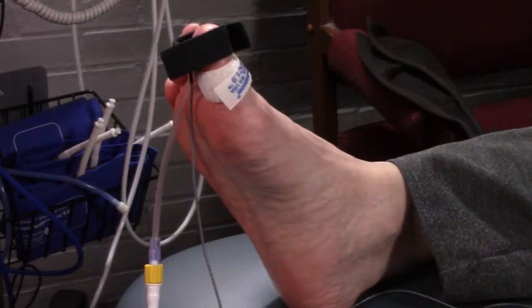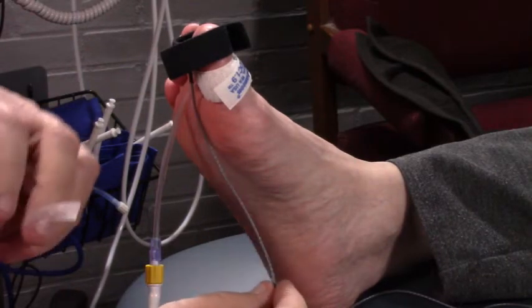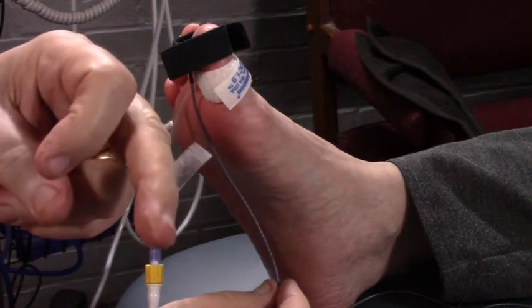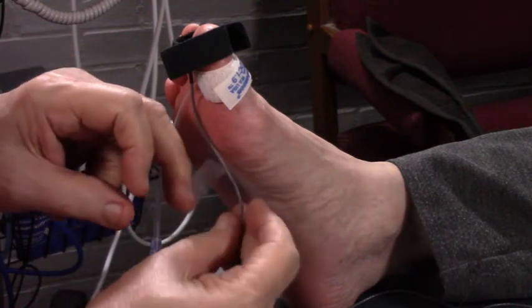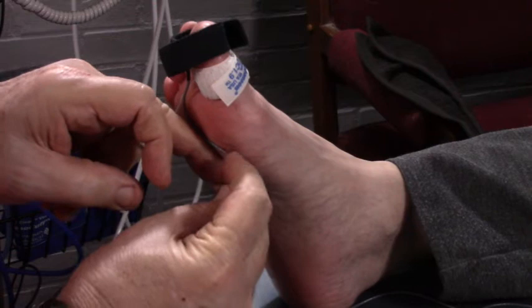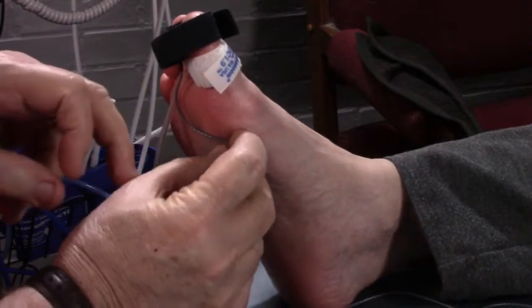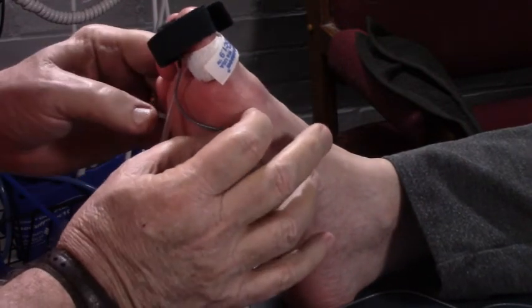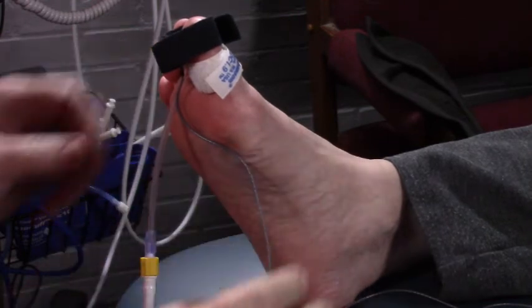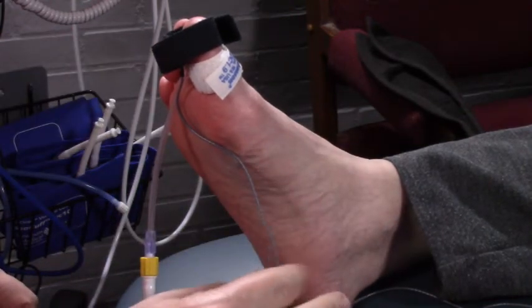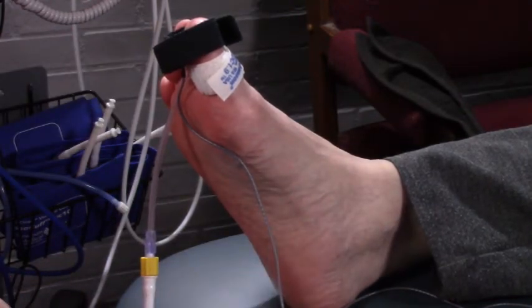Also, the PPG sensor can become dislodged from the pad of the toe and allow light to interfere with the signal quality by pulling and tugging on the connector cable. To ensure this doesn't happen, simply create a small stress loop with the cable by giving it a little slack and anchor the cable to the bottom of the foot using a small piece of tape.